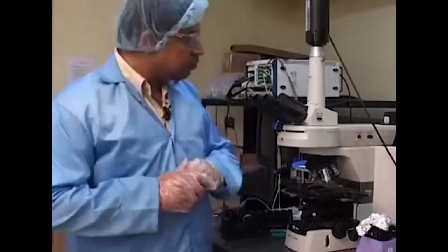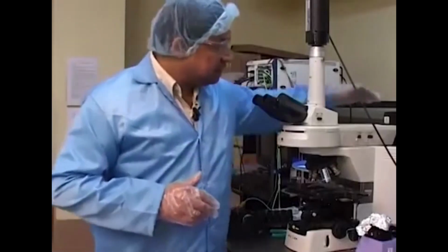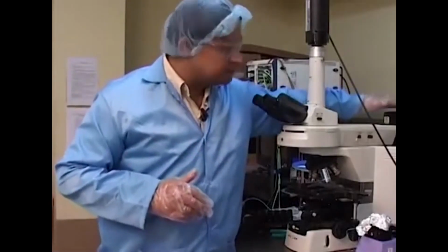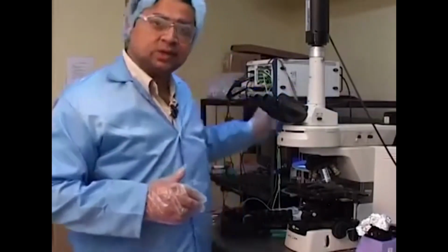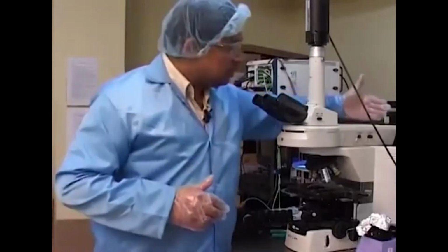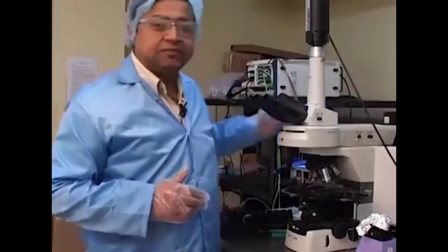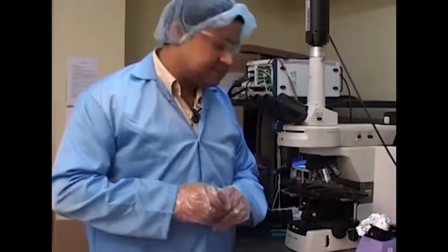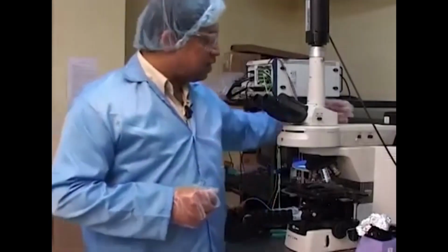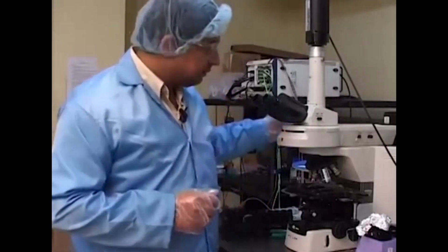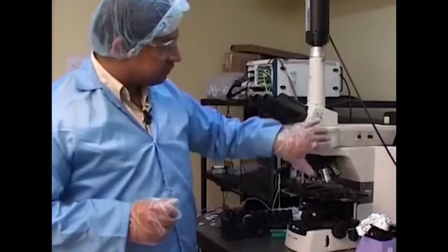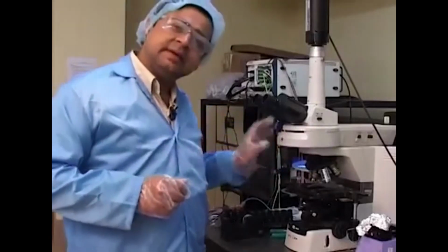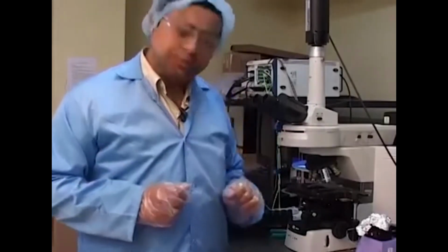The way this microscope operates is pretty simple. You have an illumination source in the background, which is a UV source. It passes through a set of ND filters, neutral density filters, which cut the UV light to different intensities. Then the light, at a much lower intensity, reaches this portion of the microscope, which has what are known as filter cubes.